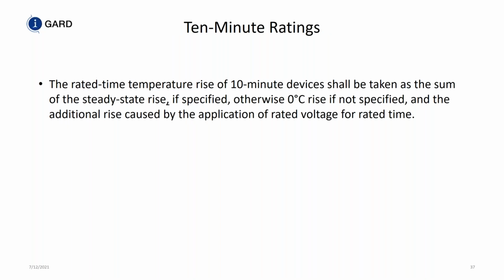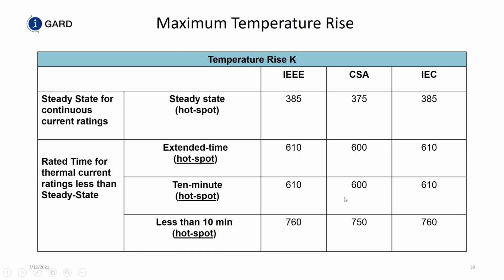10-minute rated resistor, same thing. So here are the temperature rises according to IEEE, CSA, and IEC. IEEE for a steady state, continuously rated resistor, the maximum temperature rise is 385 degrees C above an ambient of 30 degrees. CSA has 375 degrees C above an ambient temperature of 40 degrees C. So there's a 10-degree difference in ambient between IEEE and CSA. That's why there's a 10-degree difference in the CSA code as opposed to IEEE.